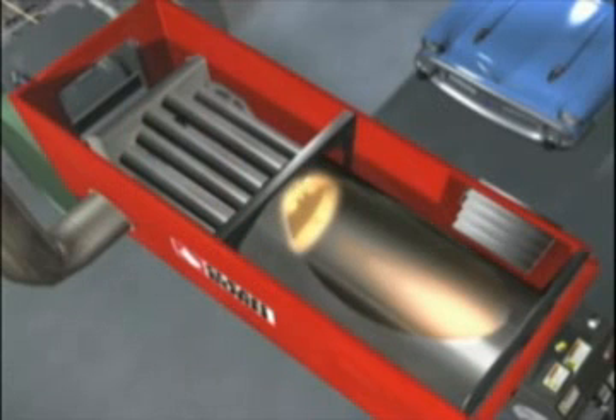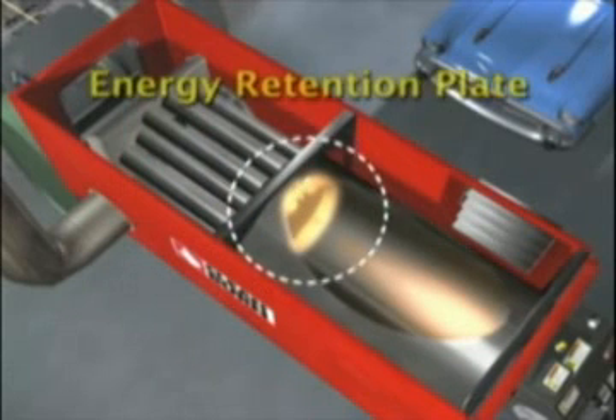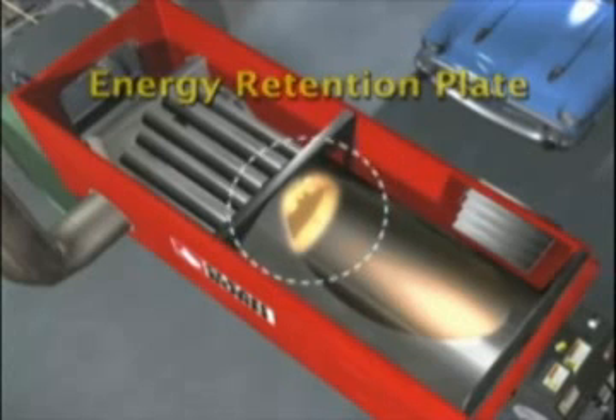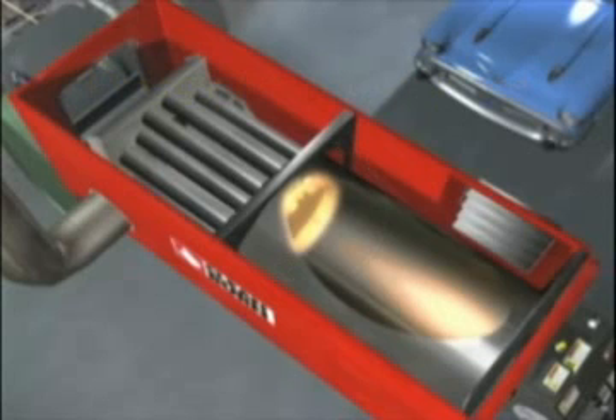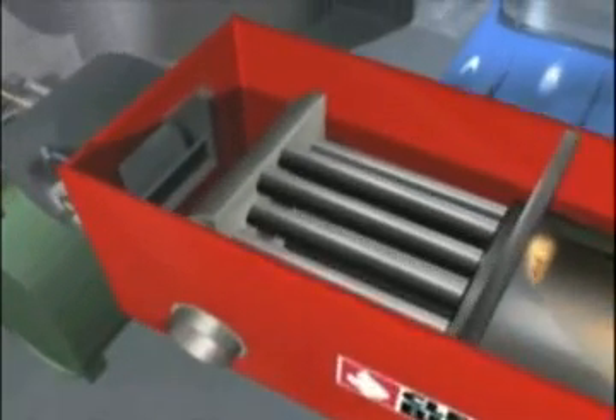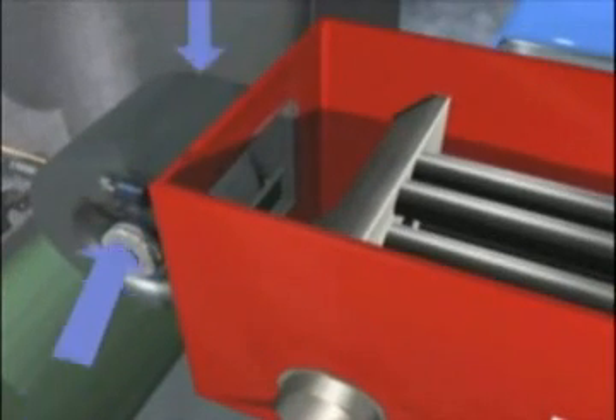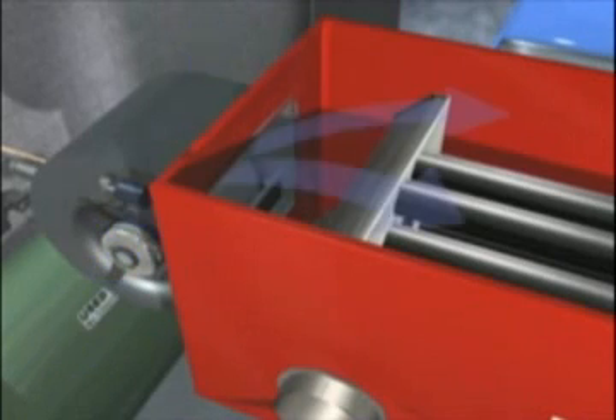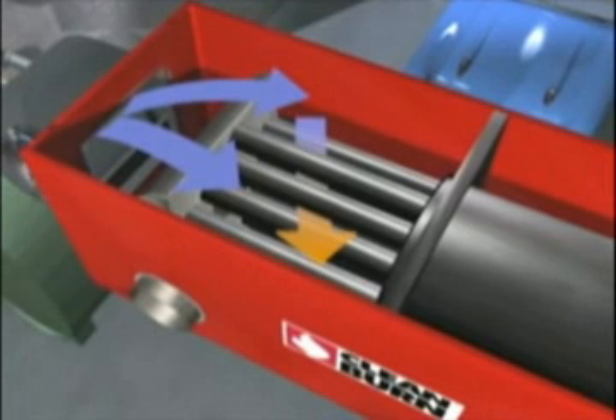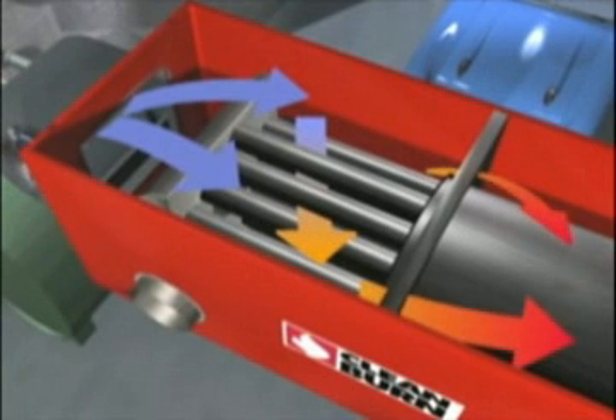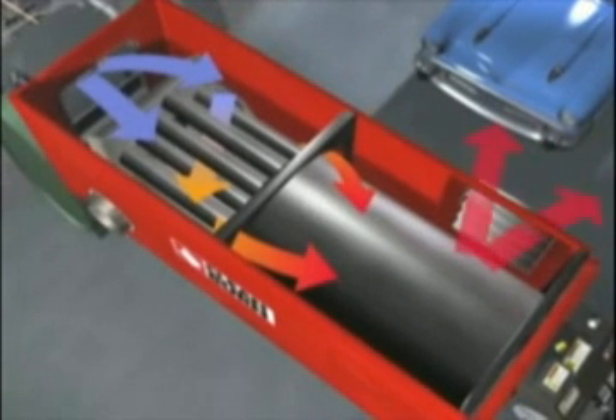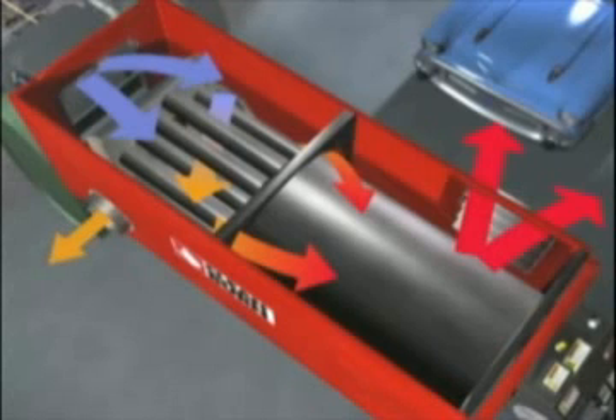Combustion takes place in a large blast chamber. At the opposite end is an energy retention plate made from innovative, heat-durable material that reflects heat back into the combustion chamber while protecting the furnace. The heat ultimately moves over and around the energy retention plate and into the heat exchanger's multi-pass tube array. CleanBurn's heavy-duty blower draws in cold air and passes it over and through the multi-pass heat exchanger's tube array and around the blast chamber, giving it ample time to absorb maximum BTUs. The heated air exits through the louvered vents, comfortably warming your shop environment.